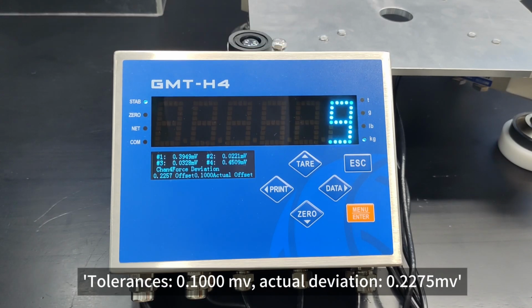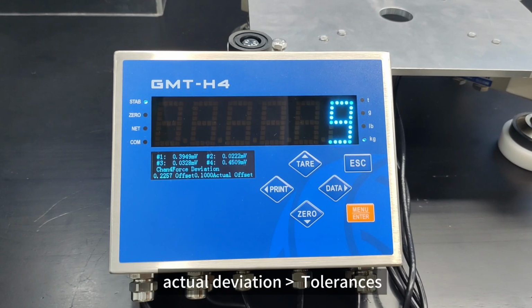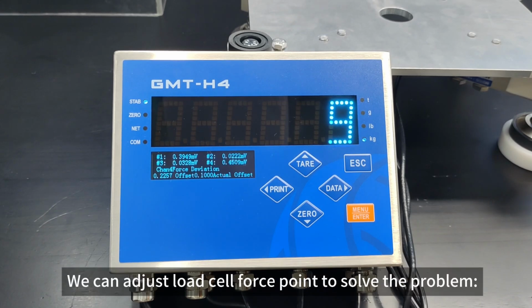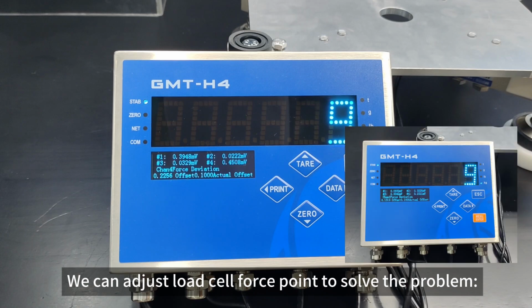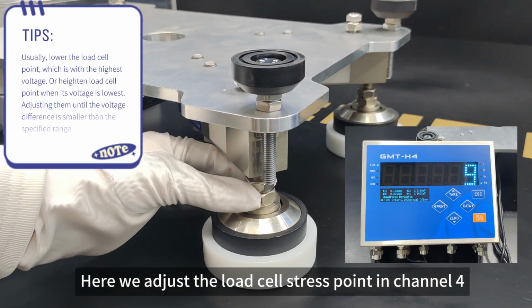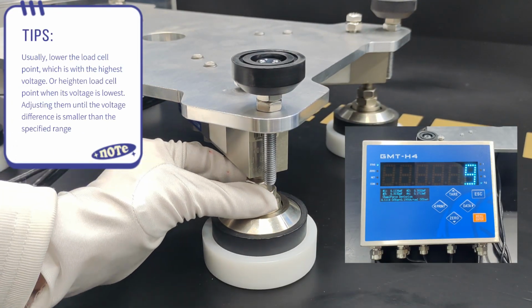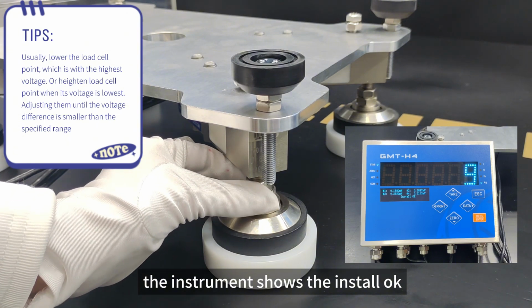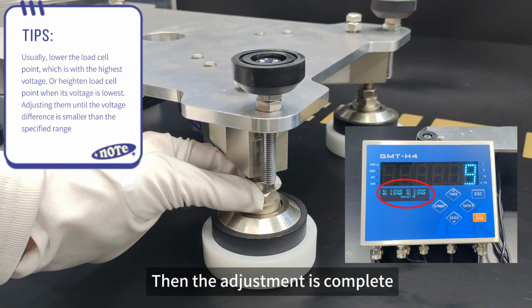Tolerances 0.100 millivolt. Actual deviation 0.2275 millivolt. Actual deviation is greater than tolerances, so the load cell force is uneven. We can adjust the load cell force point to solve the problem. Here we adjust the load cell stress point in channel 4. The instrument shows install okay. Then the adjustment is complete.